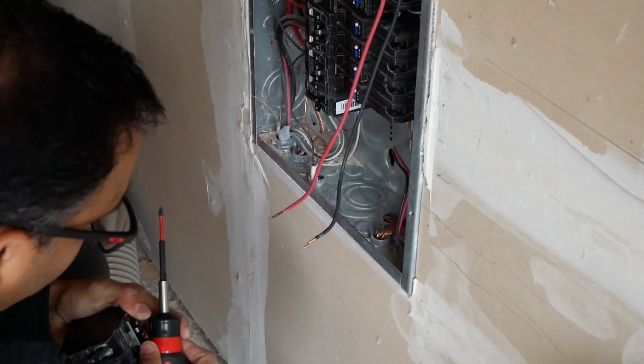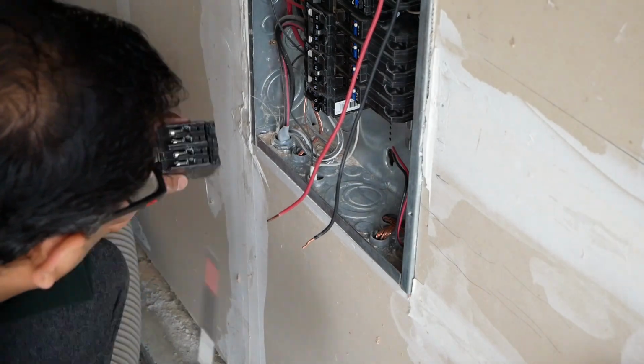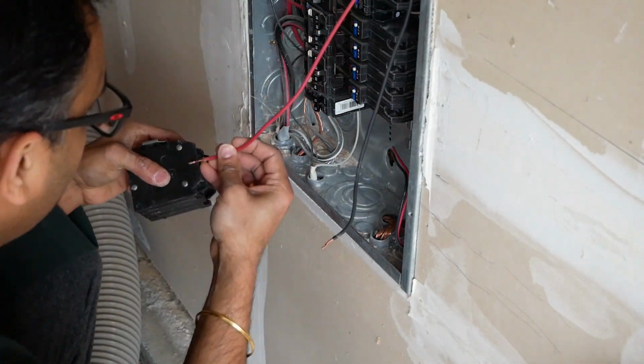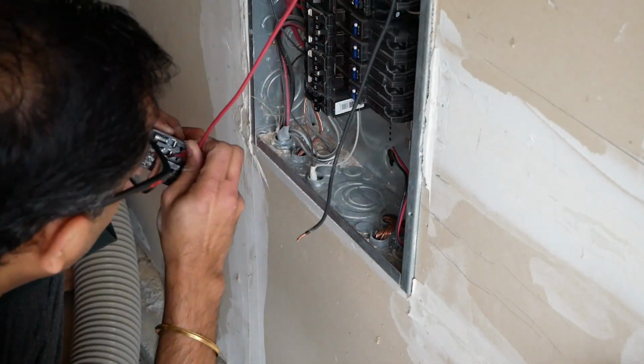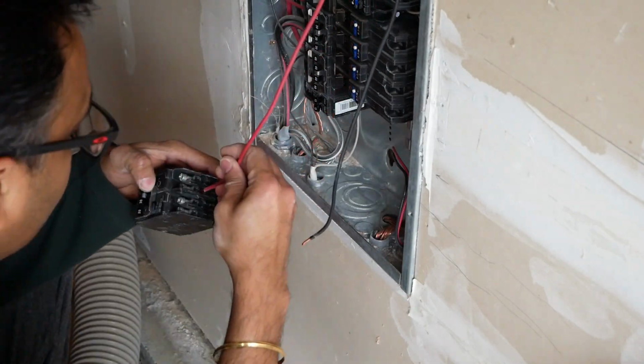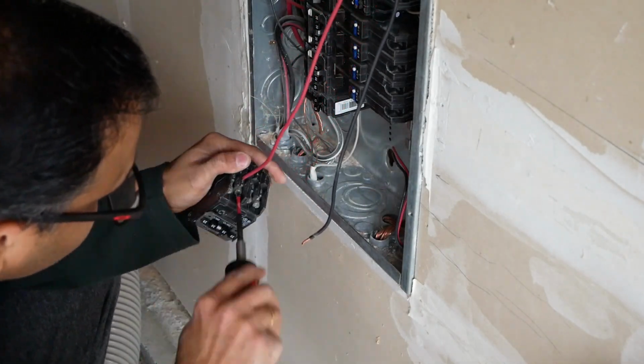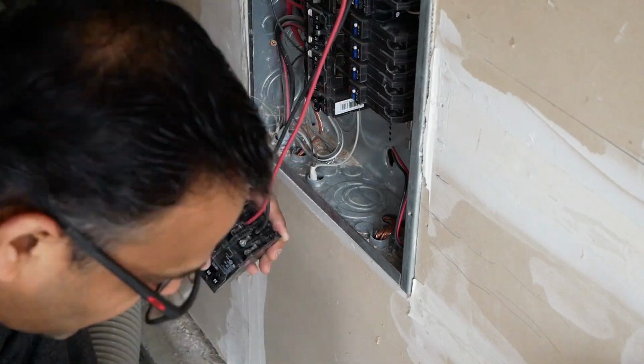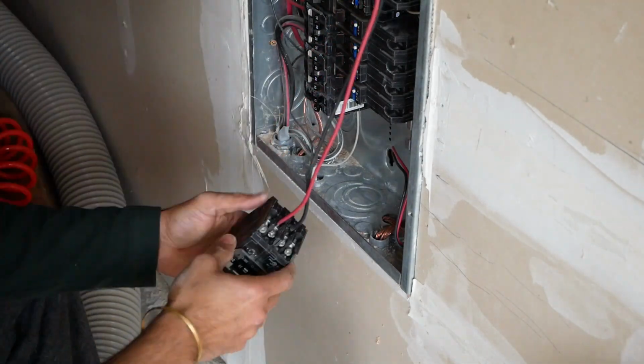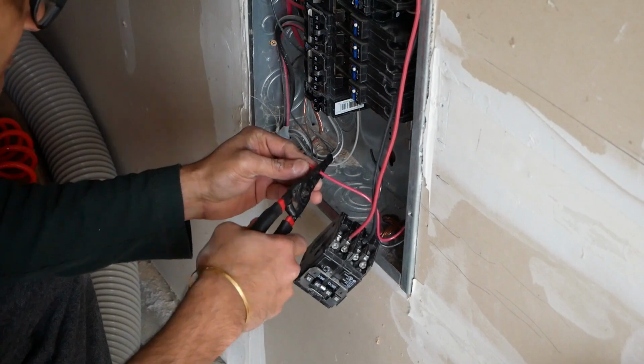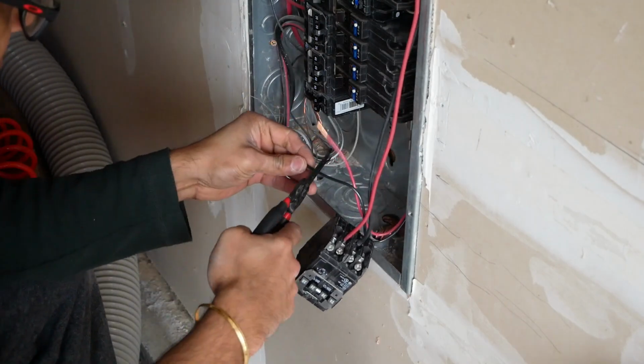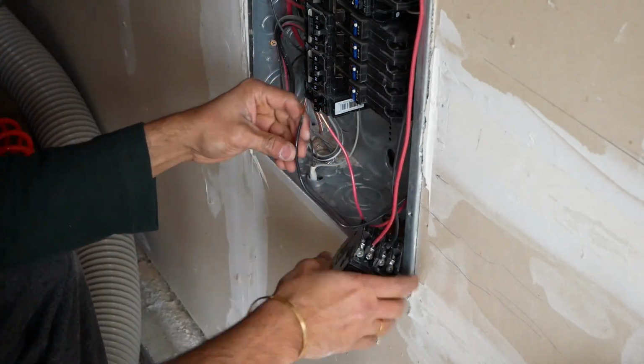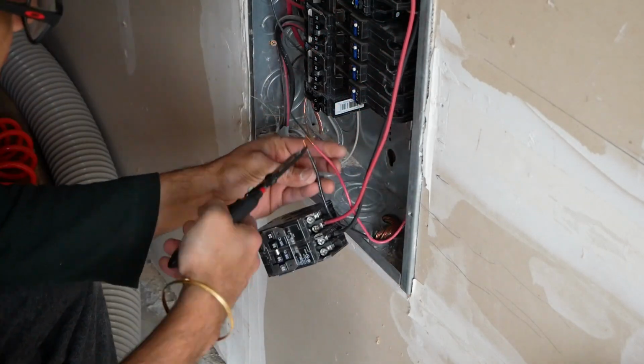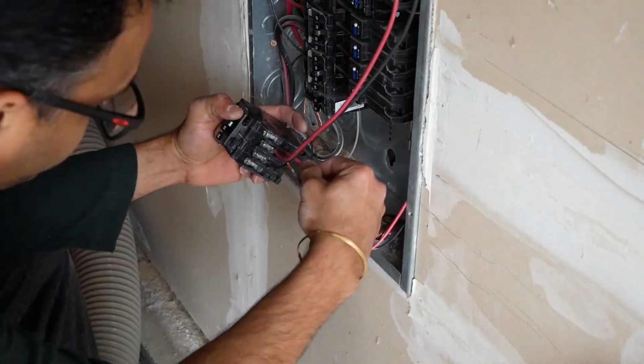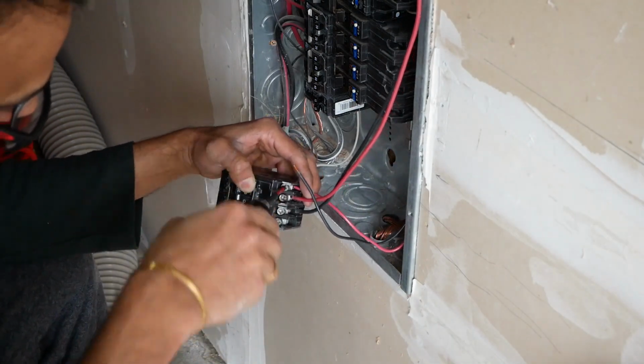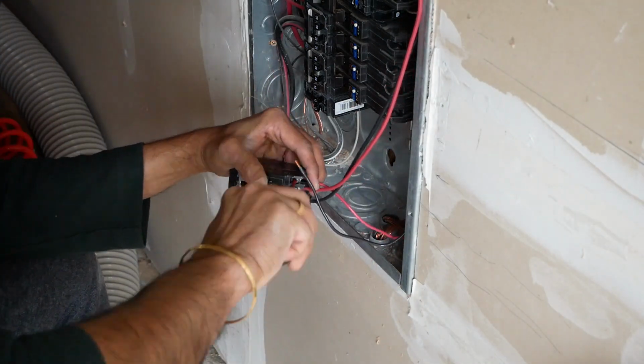Once the neutral and the ground wires are connected, we connected the two hots on the circuit breaker. Here we are connecting the original dryer wires, and after that we connected the new wires that we ran through. The original wires were a bit longer, so we trimmed them back to make sure that they are not overexposed out of the circuit breaker. Once it's connected, we connected the new wire, which was for the 20 amp. Here you see the 30 amp is going into the center 2 connection and the 20 amp is on the outer side. It's a good idea to make sure that the wires are tightened properly.